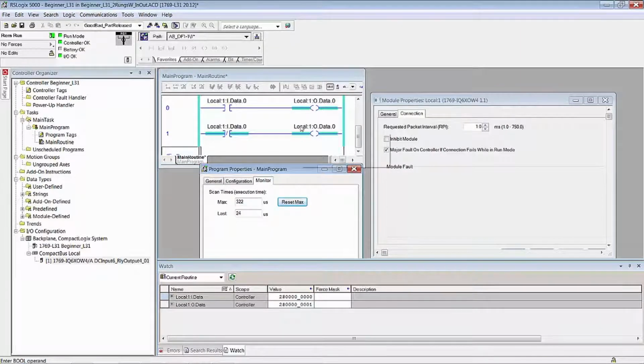But I'm not hearing it because the state is changing for such a short period of time that the relay contacts don't have time to energize. If I look at the output LED on the I/O module, I may or may not ever see that output flicker on. Because remember that even though LEDs are very, very, I just saw a tiny flicker. Even though they're very responsive, it's not like an incandescent light bulb.